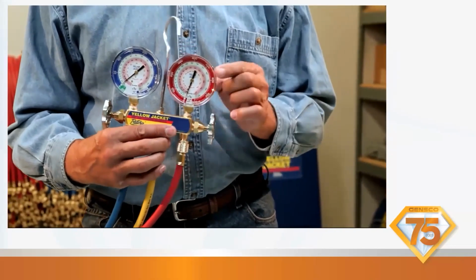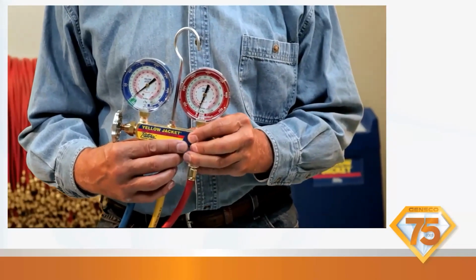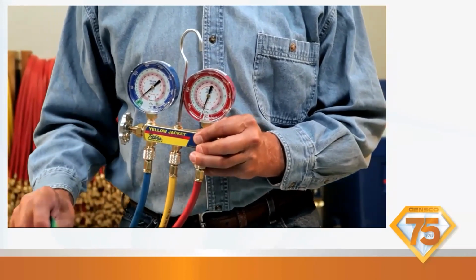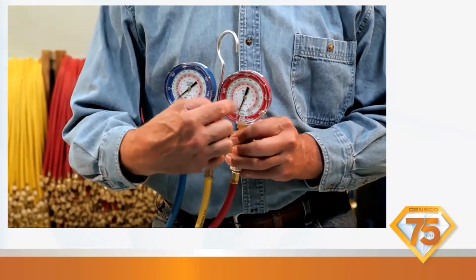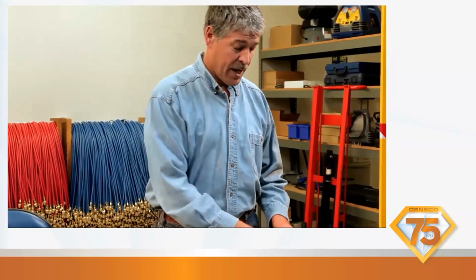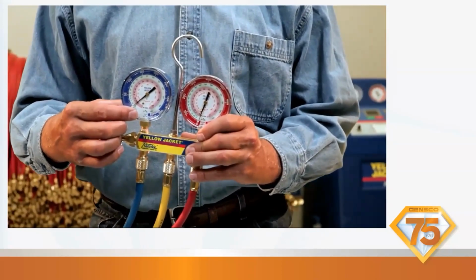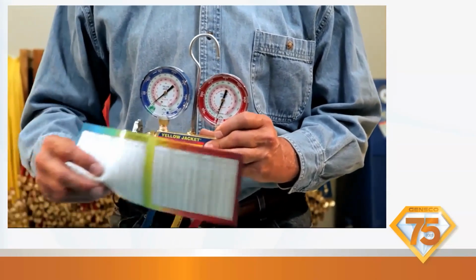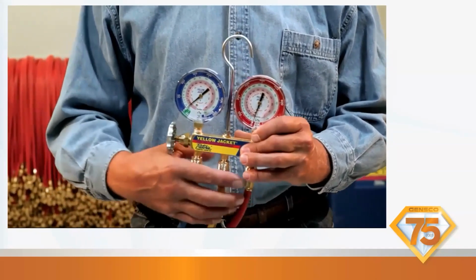Now that we've gone through the definitions, let's review how you measure them. Subcooling is determined by using the high side manifold gauge to measure the pressure of the condenser. This pressure must then be converted to a liquid saturation temperature using a PT chart or the temperature scales on the gauge. Next, measure the actual liquid line temperature using an accurate temperature probe and subtract it from the liquid saturation temperature. The result is the subcooling value. Conversely, superheat is determined by using the low side gauge to measure the pressure of the evaporator. This pressure must then be converted to a vapor saturation temperature using a PT chart or the temperature scales on the gauge. This temperature is then subtracted from the actual suction line temperature measured using an accurate temperature probe. The result is the superheat value.